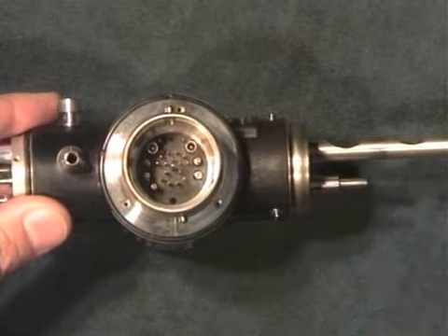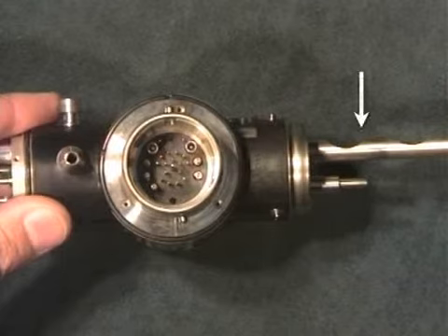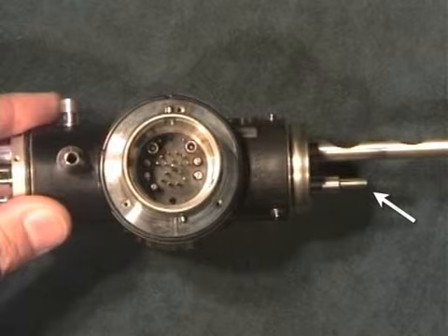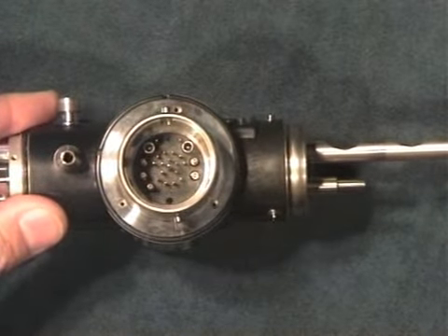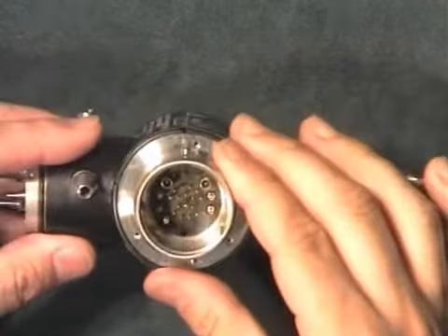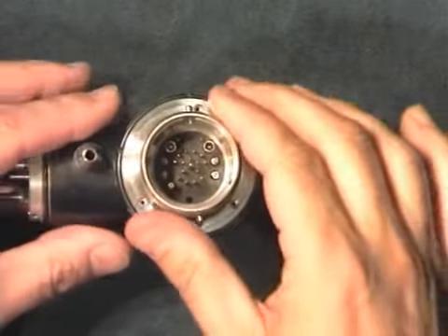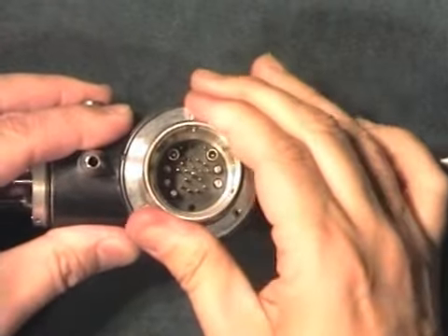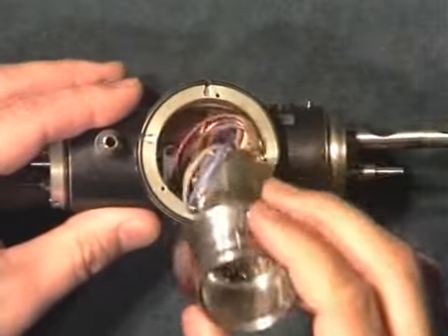The light guide plug contains, as well as the suction and water bottle connections, the metal probe covering the light guide, with the fibre bundle inside it, and the air channel probe. Finally, the pin unit, if removed, covers 3 sets of wires, from the CCD, the control switches, and the light control system.